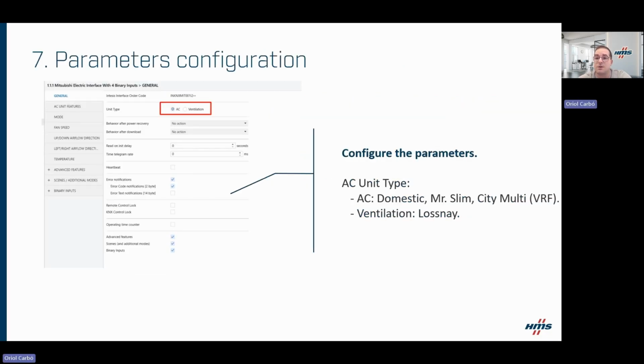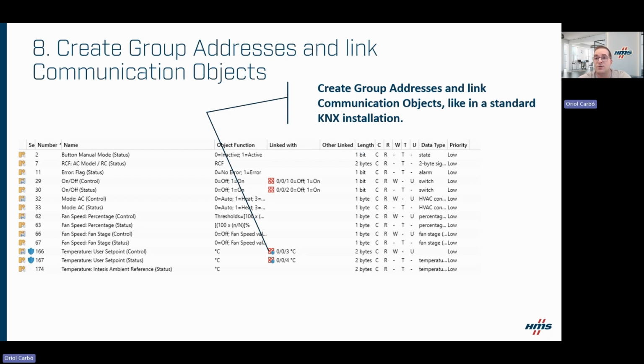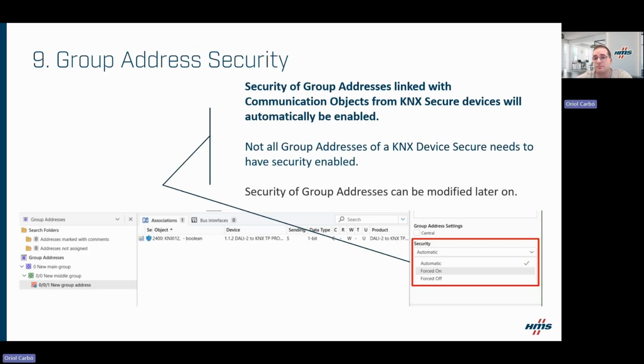And after that, you configure parameters. For example, you select the AC unit type: domestic, Mr. Slim, City Multi VRF, or ventilation like Lossnay, and also Ecodan in case you've chosen this product database. Then you create group addresses and link communication objects, basically the standard KNX workflow that you already know. And security is automatically enabled for group addresses linked to secure devices. Not every group address necessarily needs to have the security enabled, and you can adjust security later if it's needed. So it's up to you to decide about that.